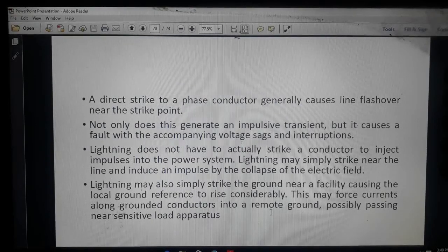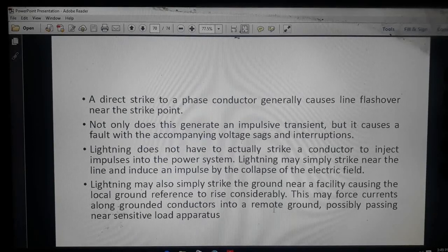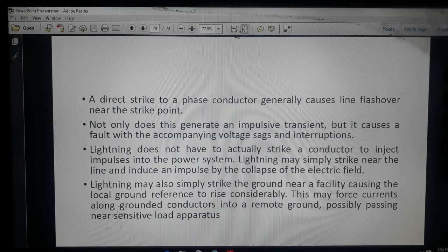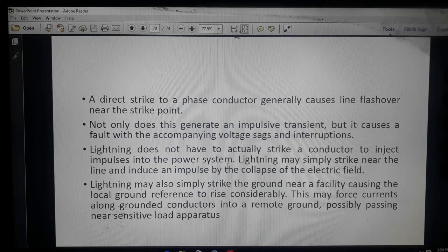A direct strike to a phase conductor generally causes line flashover near the strike point. If lightning directly strikes the phase conductor, it may generate flashover near the strike point. Not only does this generate an impulsive transient, but it causes a fault with accompanying voltage sag or interruption. Lightning does not need an actual strike on the conductor to inject an impulse into the power system.